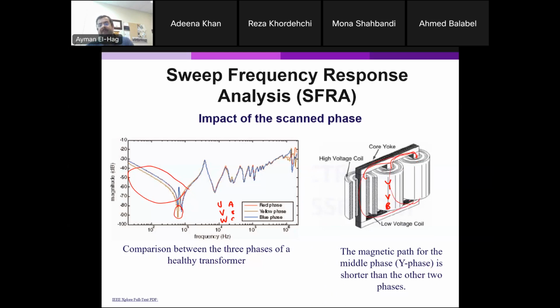It's a longer path of magnetic material. So the core seen by the winding is different. And this is why the two extreme phases see the same amount of core, as opposed to the middle phase. And this is why they have a difference. So this is not because there is a defect, but because of the natural design of the core type transformer. So this is something you have to watch.